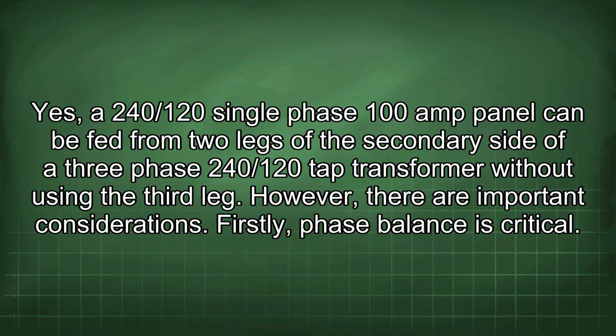Yes, a 240/120 single-phase 100 amp panel can be fed from two legs of the secondary side of a three-phase 240/120 tap transformer without using the third leg. However, there are important considerations.